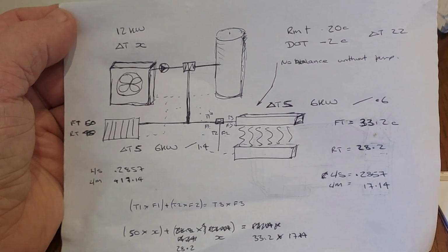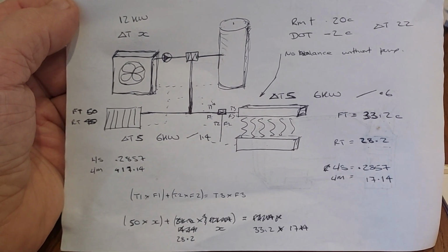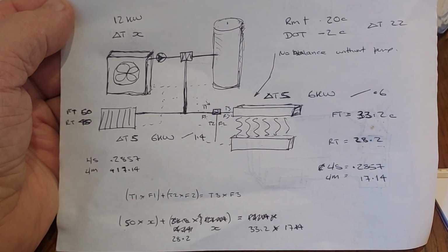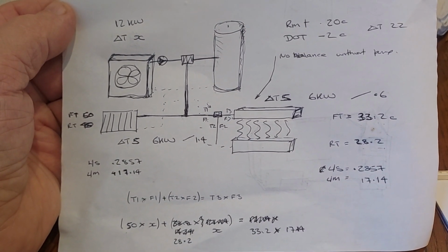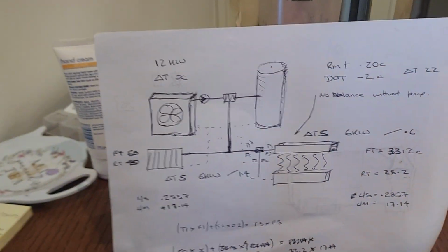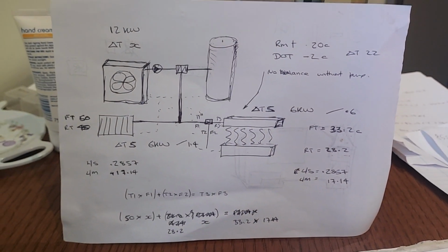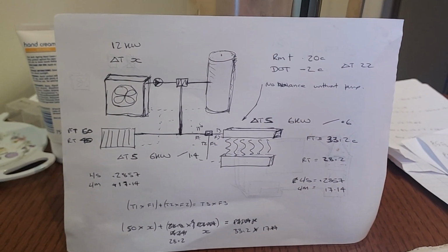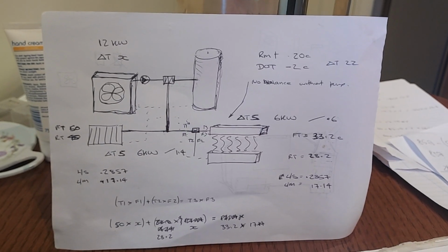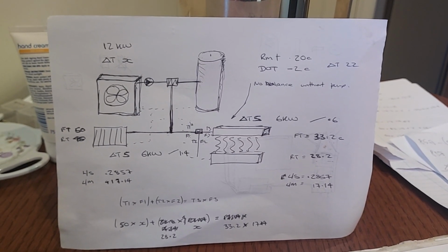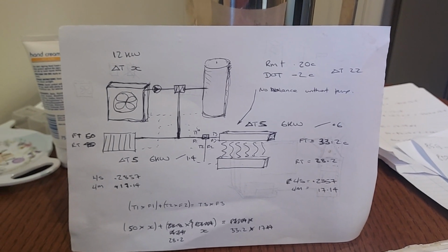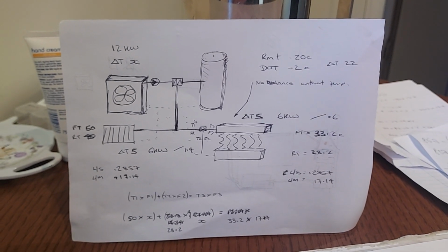And this is my conundrum on heat pumps at the moment. We need some system that not just controls the heat pump, but that controls the flow rates and the balancing of the system, all as one system, like Viessmann do more or less for their mixed systems with their boiler. Well, kind of. But what we need is a system whereby we can control the pumps after the buffer to make sure we keep the correct flow rates in the system at all times. And we need those flow rates to be variable as the flow rate from the heat pump varies.